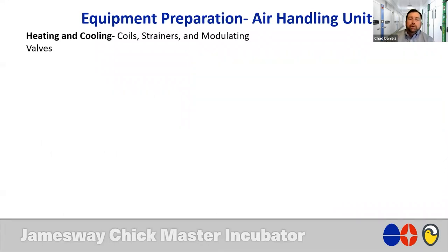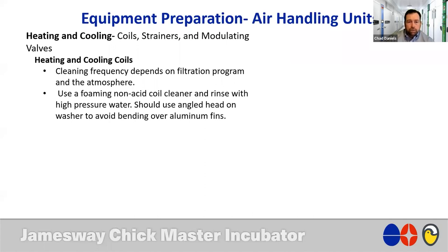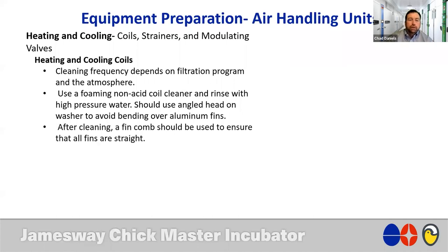So when we jump into our heating and cooling coils, you'll notice I also mentioned strainers and modulating valves, because with chilled water or hot water flow, normally that flow is regulated and the cooling or heating capacity is regulated by a modulating valve, which makes it different than a compressor on an HVAC unit. So with heating and cooling coils, again, it's important to make sure that those are cleaned. Again, use the foaming non-acid coil cleaner. And then after cleaning, make sure that the fins are straight.